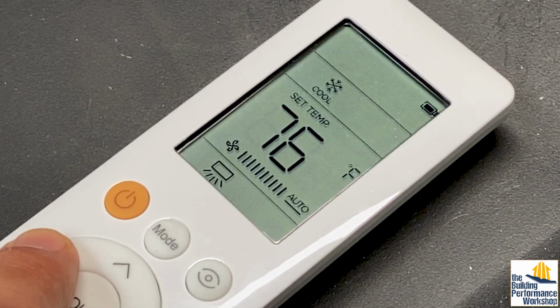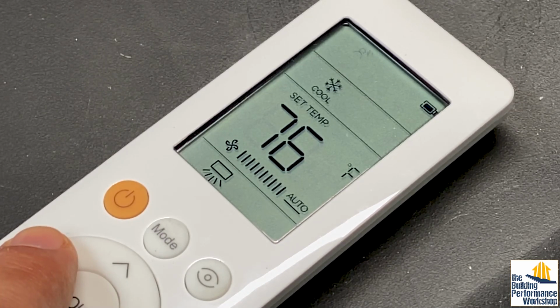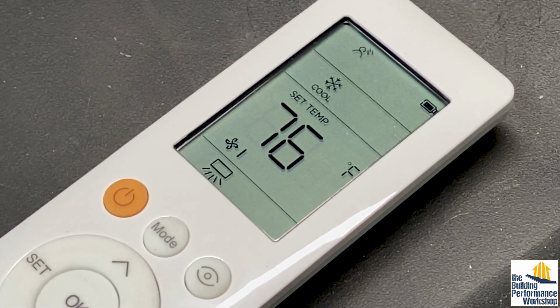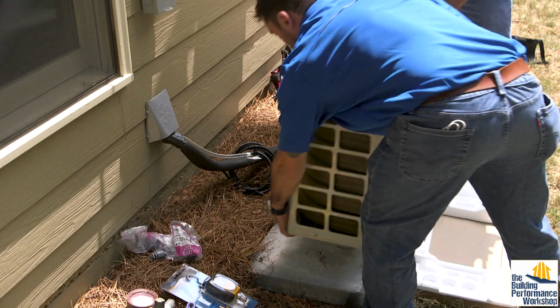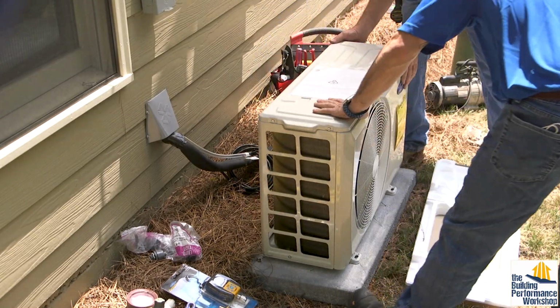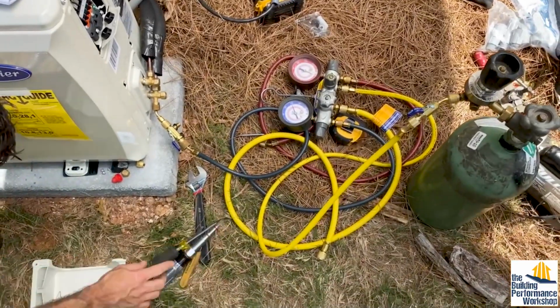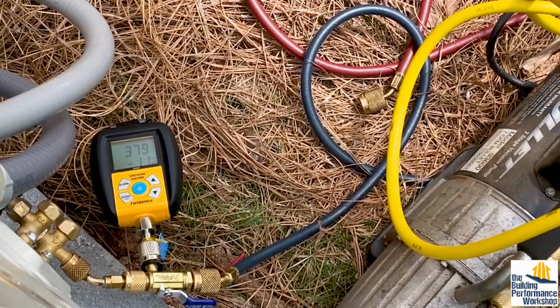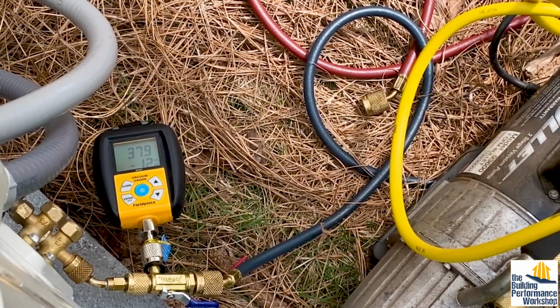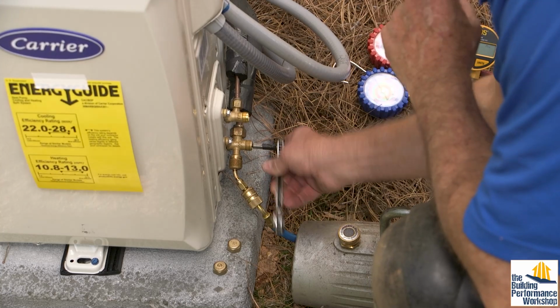Of course, they also built occupancy and light sensors into the unit, so it optimizes efficiency and can be configured to either blow on or away from the people in the room. Like most manufacturers, Carrier recommends following the latest installation techniques, like pressurizing with nitrogen to find leaks, then pulling a vacuum to 500 microns for a period of time before releasing the refrigerant.